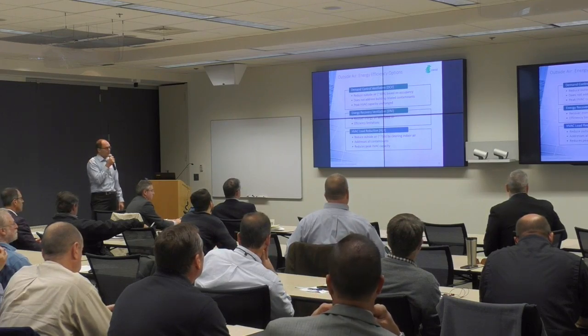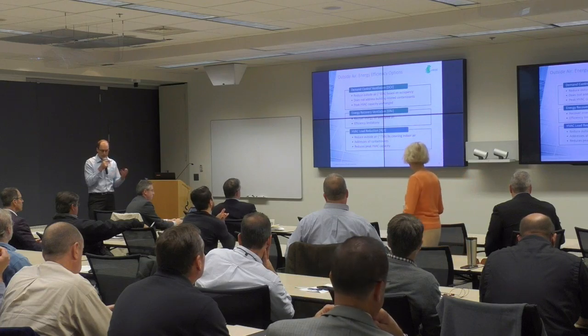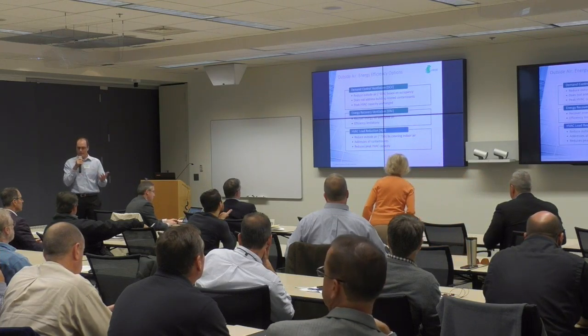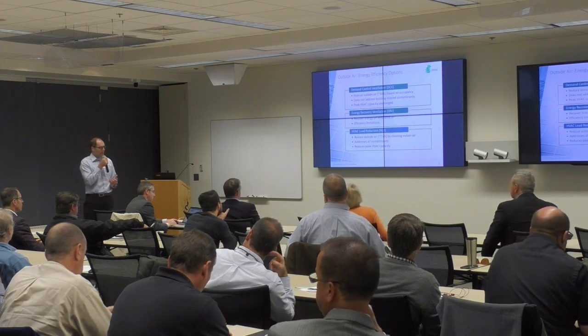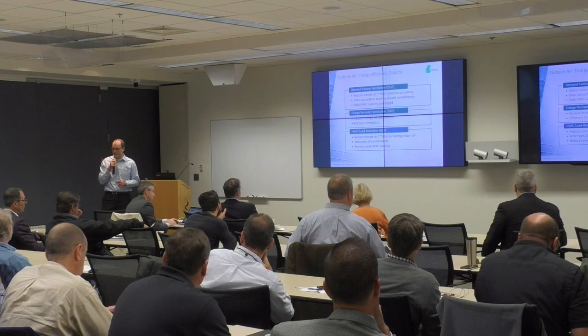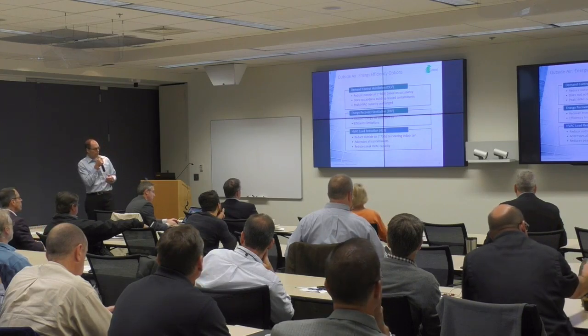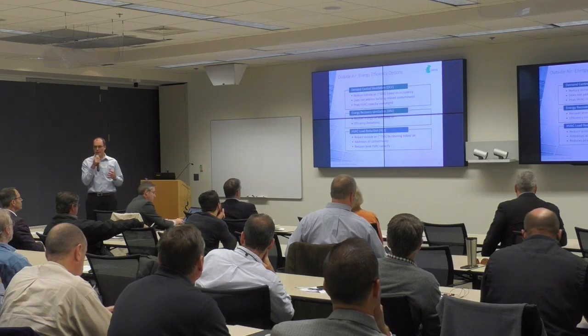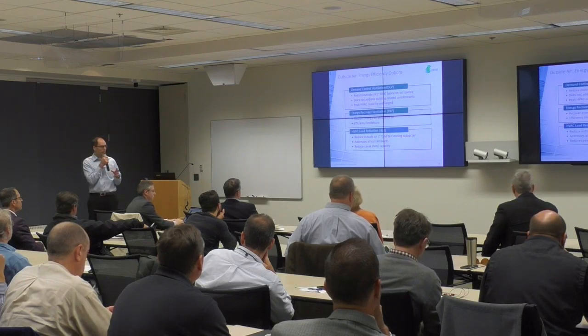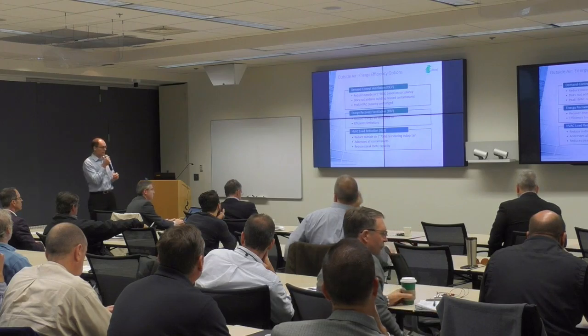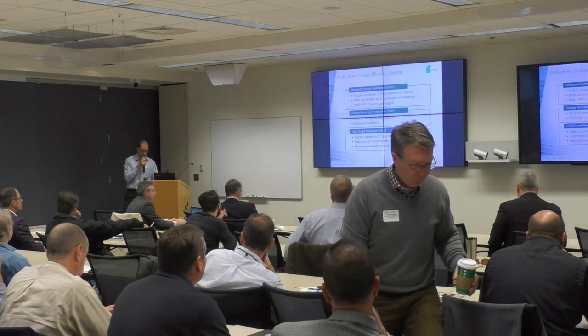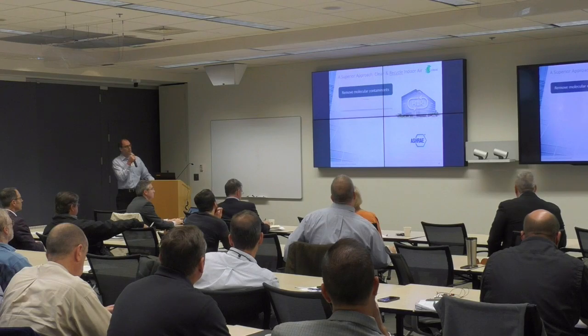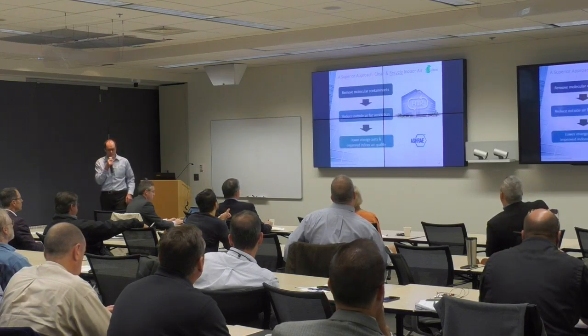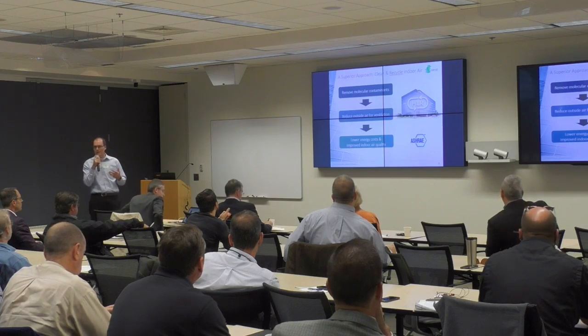Another technique is ERVs. You're recovering energy from the exhaust air and transferring that into the outside air coming in, but there are some efficiency limitations. So a new technology that's evolved is HVAC load reduction, or HLR. Here you can actually reduce outside air by a significant amount, typically 75%, by cleaning the indoor air. It addresses all the contaminants inside the building, and it allows you to reduce the peak HVAC capacity, so you can use it on a hot afternoon when you have peak occupancy. It's really a superior approach, because you're cleaning and then recycling the indoor air.